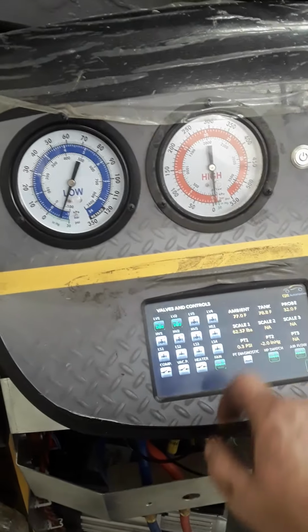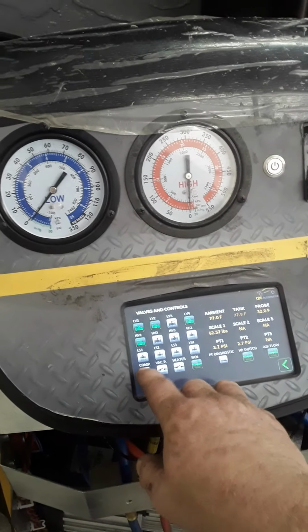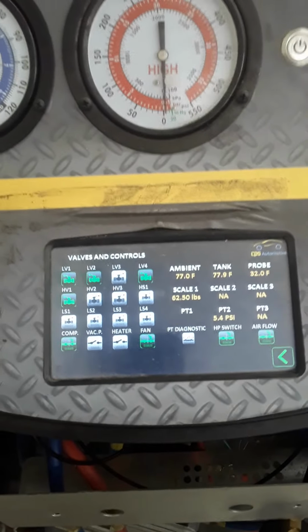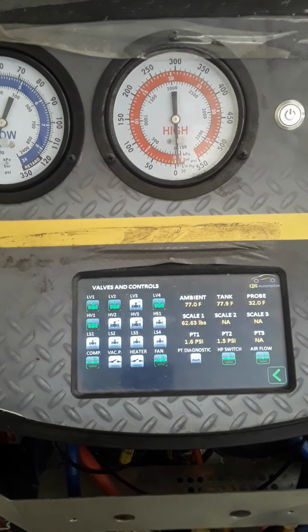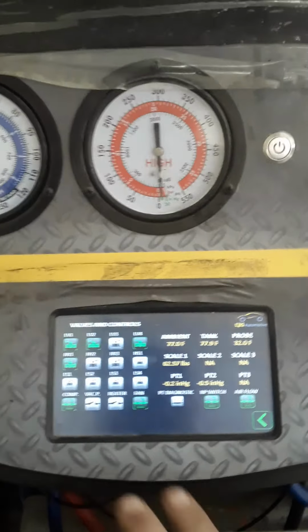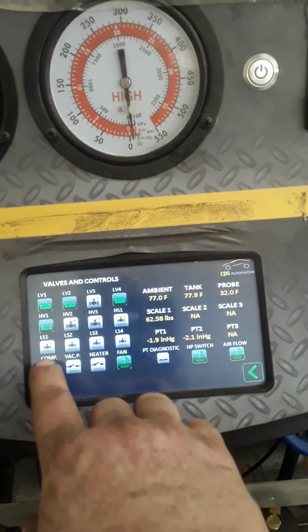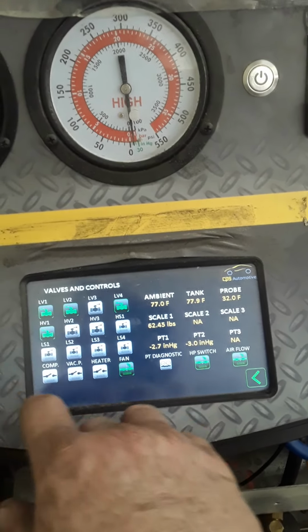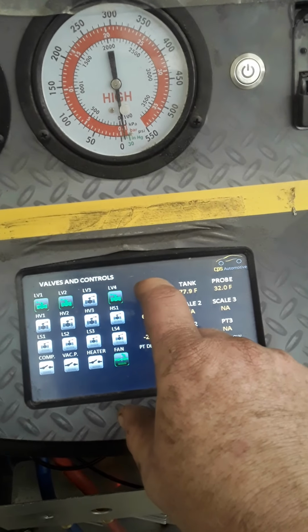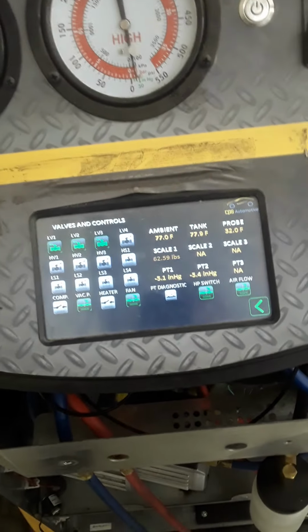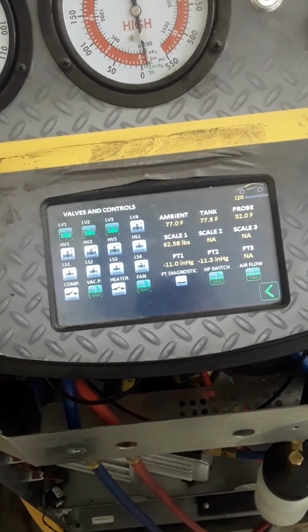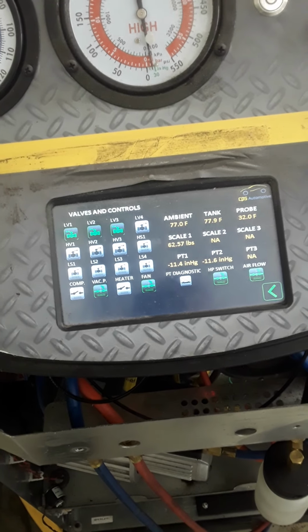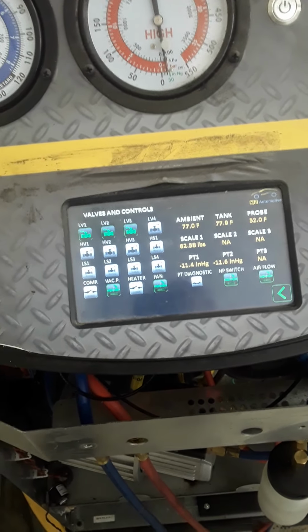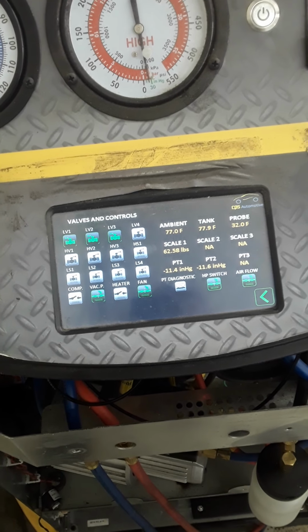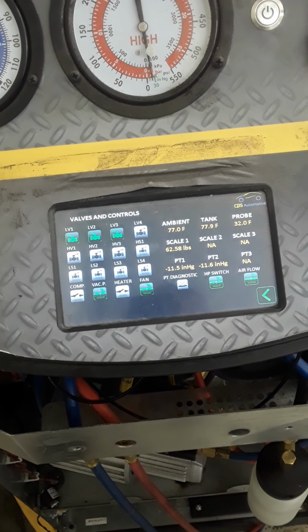Okay. So that's good. That's good that we can tackle that part. What I also wanted to tackle was that area about the pressure right now. We don't know. We can take care of that too. All of this could be in the same scenario. With that thing being clogged, my machine would get down to like 0.2. It would stay there at 0.2, and I could never get it to change. I changed the main control board, I changed the PT board, I changed everything I could change on it. But I ended up having to take that brass cylinder out of that PT and replace it because I didn't have a wire small enough to unclog that hole. And that was the problem.